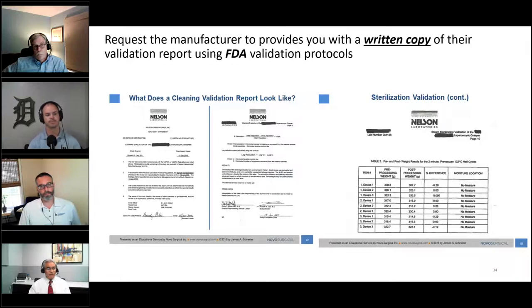So in this, you see they selected three instruments and soiled them, and after that they all showed negative. These are the documents manufacturers must submit with their 510K clearance or PMA approval. So if they have them, ask for those written IFUs to see how they validated them. And moreover, if you have an issue, you should be able to validate them yourself, or if you have a problem or a lawsuit, send those to a third party to validate them.